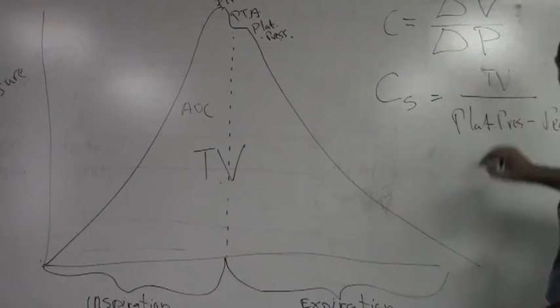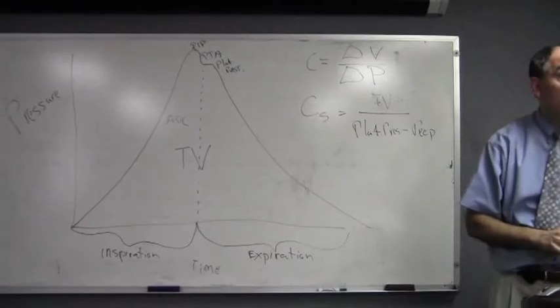If you want to be very correct, you could measure the tidal volume that's set on the ventilator and then measure the volume that's exhaled. You would need an apparatus to do that, but for all practical purposes, you can use just the set tidal volume that you've set on the ventilator, because this is technically the change in volume. So you need to know the change in volume on inspiration and expiration. But that becomes a little bit difficult. You can look at the machine and calculate and see when they exhale. I just average it out and usually just use the tidal volume that's set.